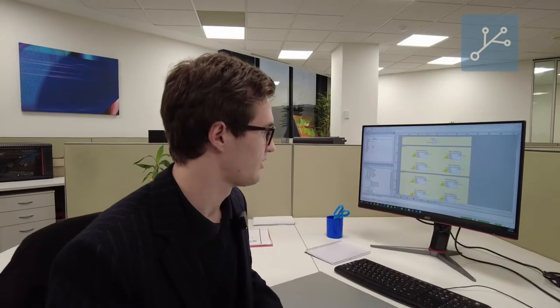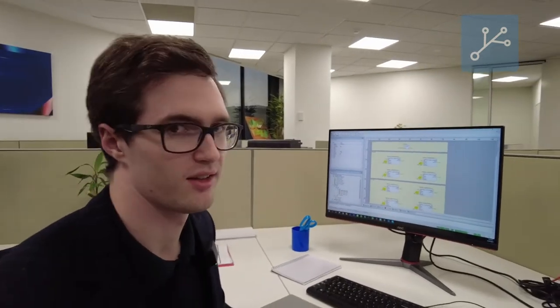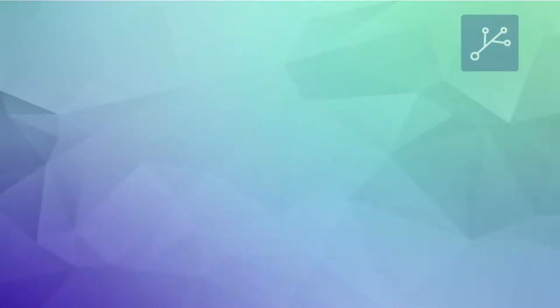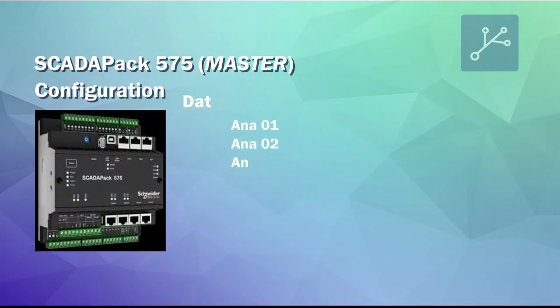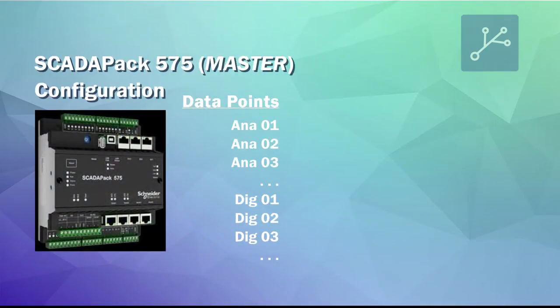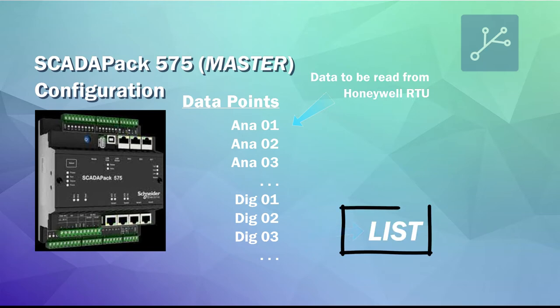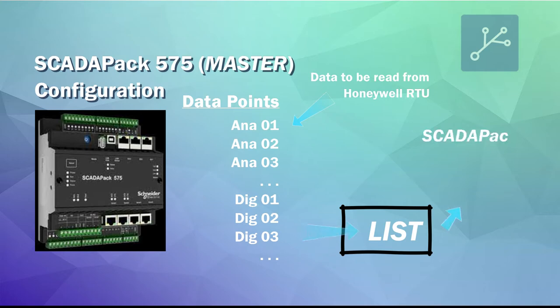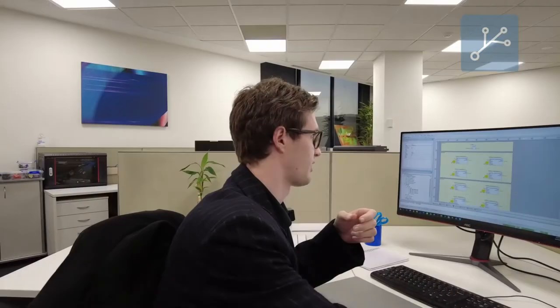So how DNP3 peer communication works: we have the master — the SCADAPack — define all the different points and values of what needs to be read from the Honeywell RTU. All these points are read into a list, it doesn't matter if it's analog or binary; it's all read into the same list which is then executed by a separate function block. I can demonstrate that here.